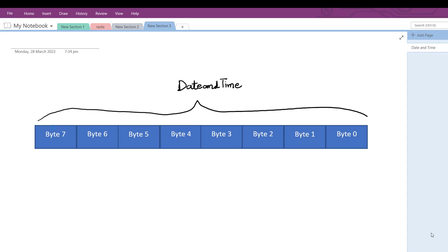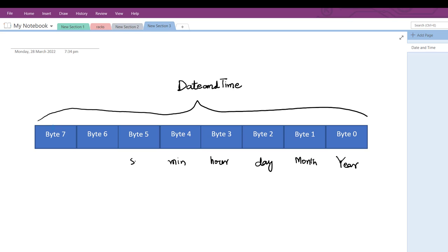In Simatic PLC programming, the DATE_AND_TIME data type is comprised of 8 bytes, that is 64 bits. If we divide it into bytes, byte 0 (the least significant byte) has the year data, byte 1 has month data, byte 2 has the day, byte 3 has hour, byte 4 minute, byte 5 seconds. The 8 bits of byte 6 plus the 4 most significant bits of byte 7 hold the milliseconds information.